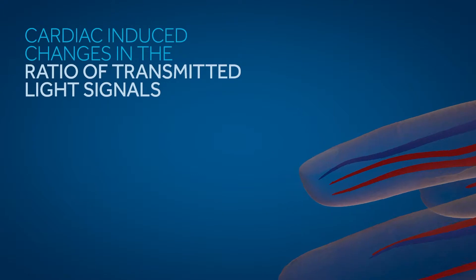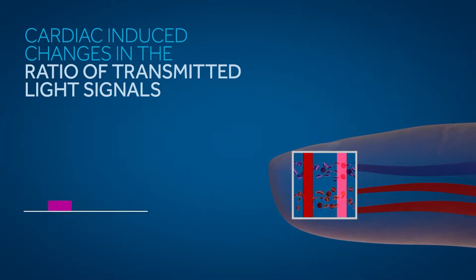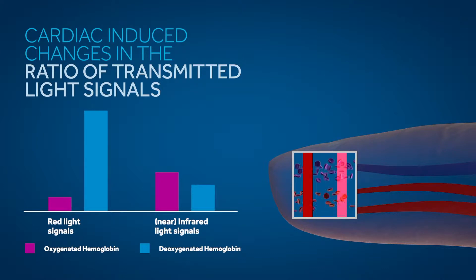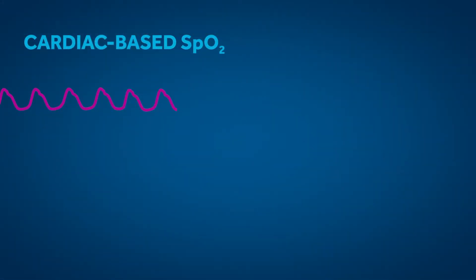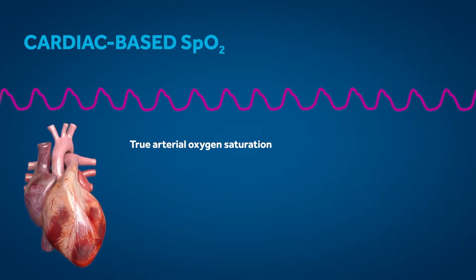Pulse oximetry is based on a predictable relationship between a patient's arterial blood oxygen saturation and cardiac induced changes in the ratio of transmitted red and infrared light signals. The methods for determining Nellcor pulse oximetry SPO2 values are founded on the fact that the patient's true arterial oxygen saturation is associated with the patient's cardiac induced pulse.